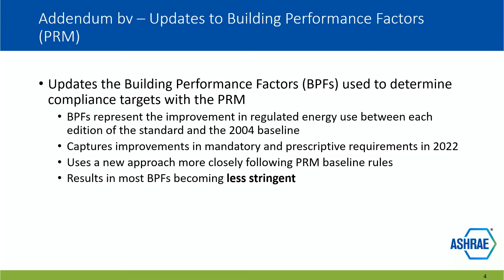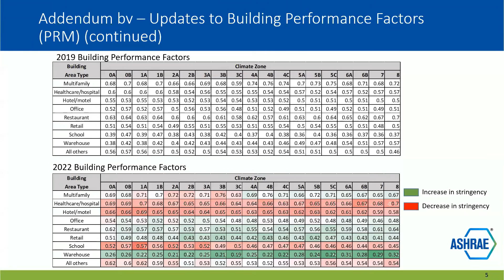So even though the standard improved in stringency, the BPFs themselves got less stringent, and that's demonstrated by the two tables in front of you. The upper table shows the BPFs from the 2019 version of the standard, and the lower table shows the BPFs in the 2022 version. The heat map's red colors represent BPFs that have gotten less stringent, and green represents those that have gotten more stringent. Some went up, some went down, but probably more got less stringent than improved. That's a pretty big difference. For those not familiar with this table, the columns represent the different climate zones, and the rows represent different building types.